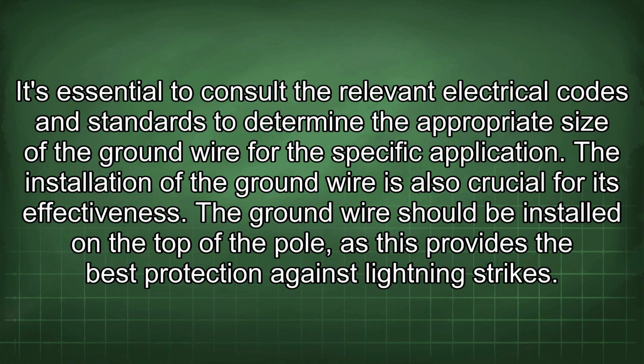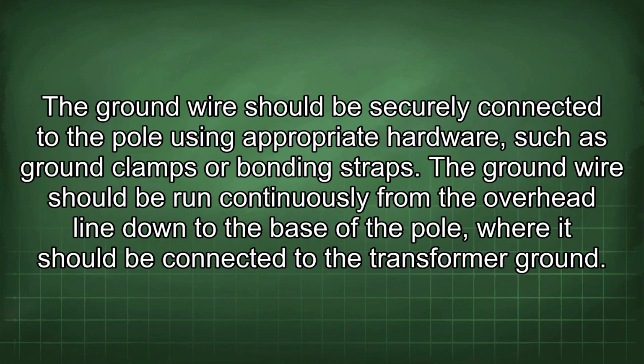The installation of the ground wire is also crucial for its effectiveness. The ground wire should be installed on the top of the pole, as this provides the best protection against lightning strikes. The ground wire should be securely connected to the pole using appropriate hardware, such as ground clamps or bonding straps. The ground wire should be run continuously from the overhead line down to the base of the pole, where it should be connected to the transformer ground.